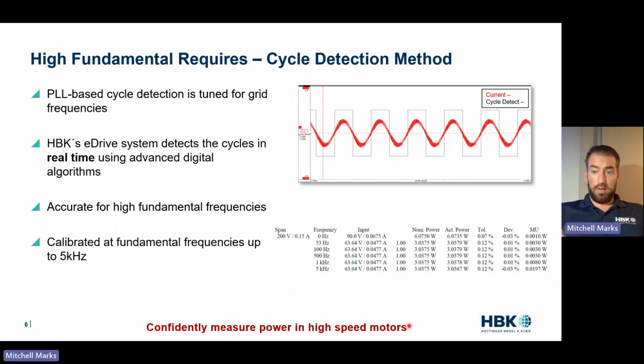So if you really want to confidently measure the power in high-speed motors, you need to make sure of the cycle detection method, because electric power requires you to have the right time period for averaging. You need to be really confident in that averaging period for high-speed motors. The accuracy is dependent on it. Also, there's a whole thing I could talk about with filters. We have some YouTube videos and some other webinars. If you're interested, please contact us, because filtering for power at high speed is also extremely interesting.